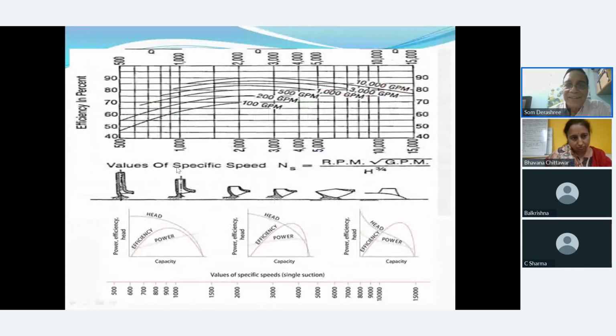No. See, the specific speed increases, 10,000 GPM is constant, but specific speed is to decide on the shape of the pump. Shape of the impeller actually, and the pump casing. So actually, every manufacturer, nobody designs a pump for your application. They have a set of models 1, 2, 3, 4, 5. If you want model 1.1, nobody will give you. You have to take either model 1 or model 2. Nobody does this kind of detailing specific to your needs. So you have to either choose pump 2, for which they will give you a curve, or you have to choose pump 1, which is what meets your requirement. But they may be slightly deviating from your specific need. Okay. Thank you.